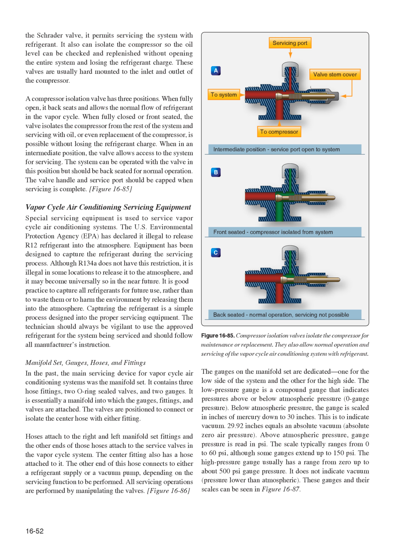Figure 16-85, vapor cycle air conditioning servicing equipment. Special servicing equipment is used to service vapor cycle air conditioning systems. The U.S. Environmental Protection Agency, EPA, has declared it illegal to release R12 refrigerant into the atmosphere. Equipment has been designed to capture the refrigerant during the servicing process. Although R134A does not have this restriction, it is illegal in some locations to release it to the atmosphere, and it may become universally so in the near future.